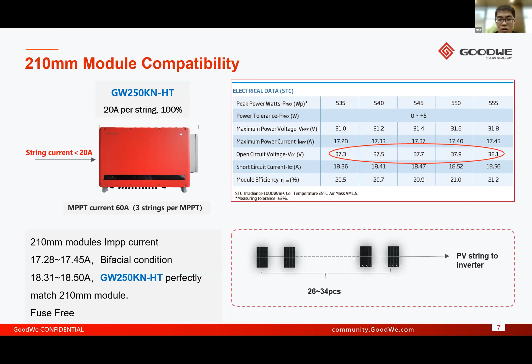You can see the string current is 20 ampere with a 3 strings design. Most clients may have the concern whether they need an external fuse to prevent 2 strings' current flowing back to 1 string when 1 MPPT connects 3 strings. Well, for the KN, we still use the non-fuse design to solve this problem. It is equipped with an intelligent DC switch, which can automatically trip when an overcurrent failure occurs. This DC switch can also receive the trip signal from the inverter DSP to shut down the DC circuit in an emergency. So we can see our new model perfectly matches 210 millimeter modules.